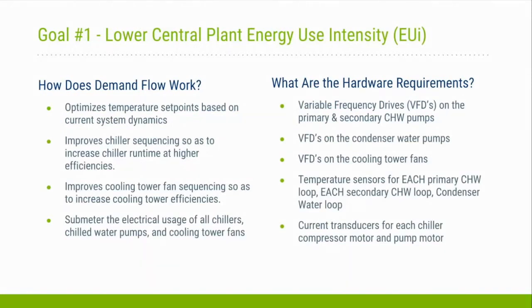For goal number 1, Ron discussed the pre- and post-installation power comparison and the improved efficiency of each chiller across its load profile. He talked a little bit about some of the sequences that demand flow tries to optimize. I want to go into a couple of other particulars about how demand flow works. First, demand flow optimizes the chill water and condenser water temperature set points and chill water flow rates based on current system conditions. The plant sees improved efficiencies at different combinations of condenser water and chill water temperatures and chiller loading. This is integral to how the demand flow algorithm increases cooling plant efficiency.